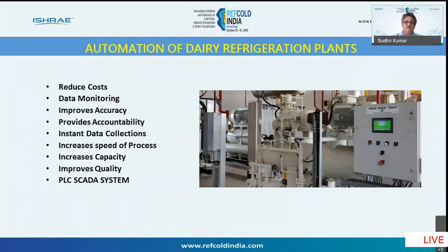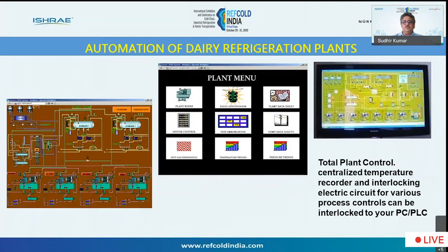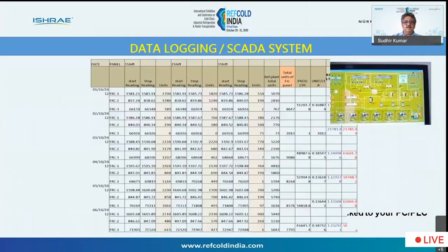We have seen a lot of dairy projects now with completely automatic operation, right from milk receipt to the outgoing also. So everything is completely captured in the SCADA system. In the SCADA system, you can see all the complete plant parameters, and also it can be operated from a single control desk. So you are avoiding a lot of operator cost, and also you are saving on the energy efficiency because you are running the plant accurately, not dependent on the operator's efficiency. So this is one of the major innovations in the dairy system.